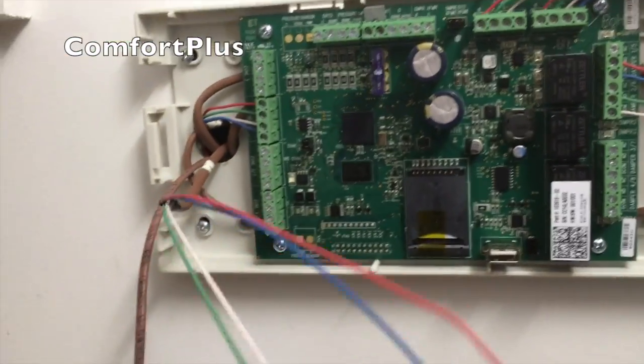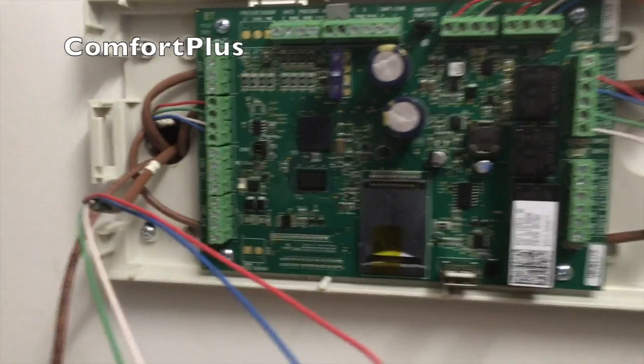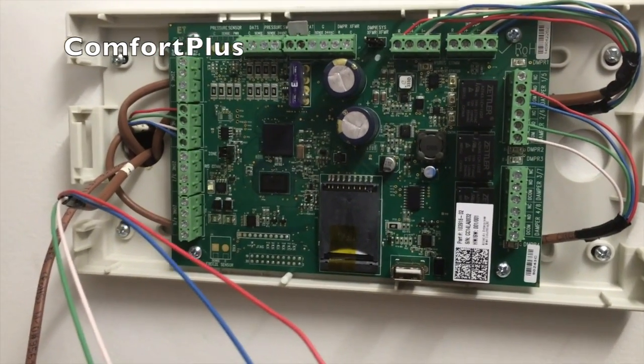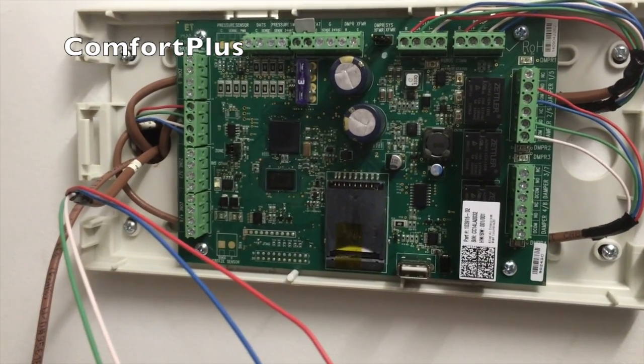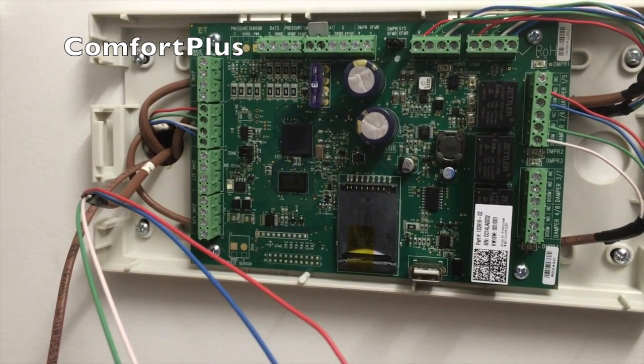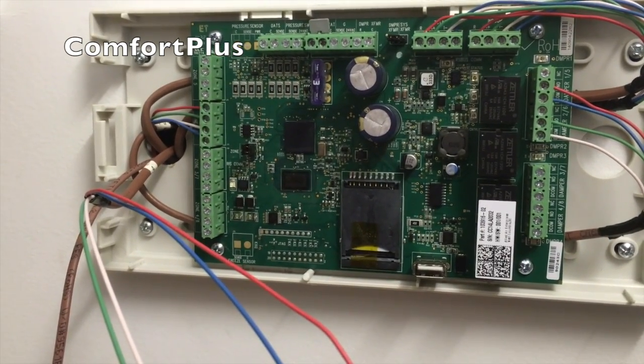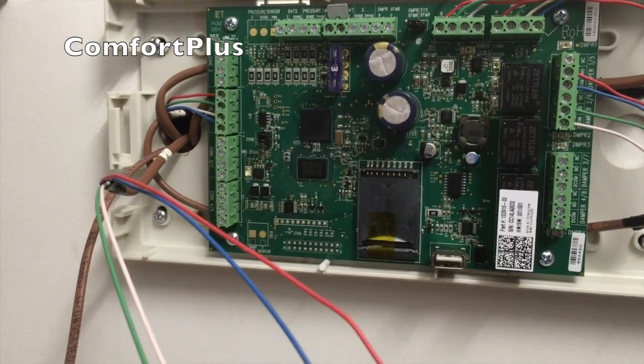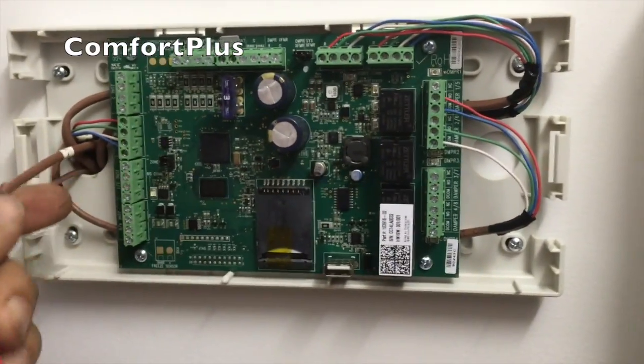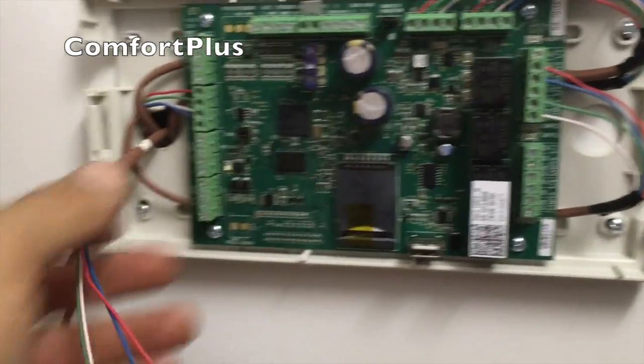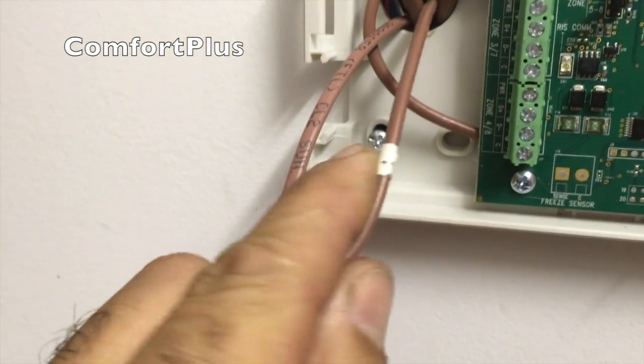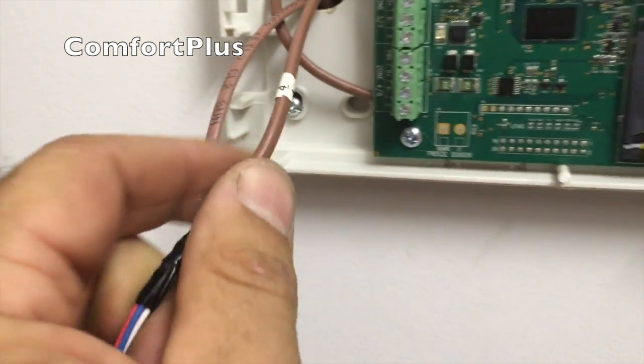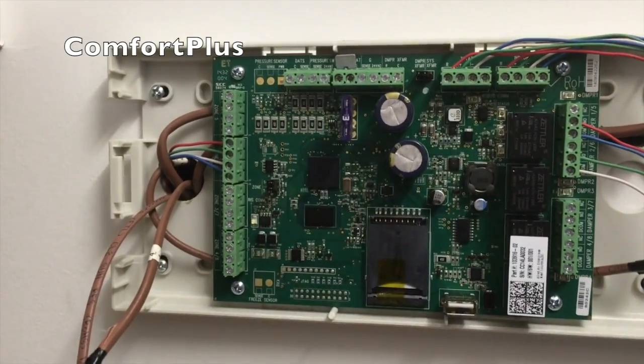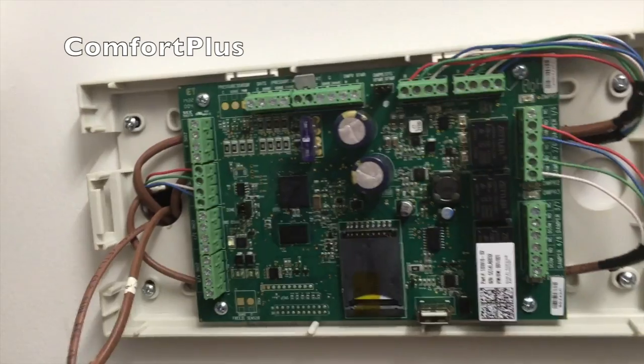I've replaced all of the thermostat wires with 4-wire cable, so I wouldn't have to worry about noise on those additional wires. Plus the original install had like 22 gauge thermostat wire, maybe 20 gauge, and this thing really wants you to have 18 gauge. So I've got my wires numbered that I've ran down underneath the house to the unit, so I'll know what's what. And I'm keeping a list of what I'm hooking up on which cable and which wire.